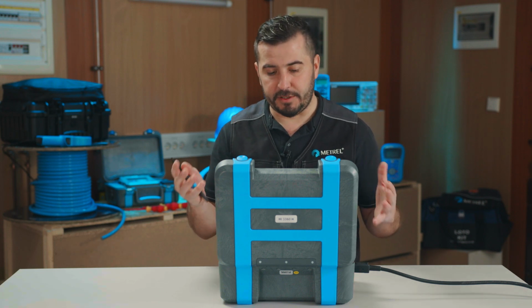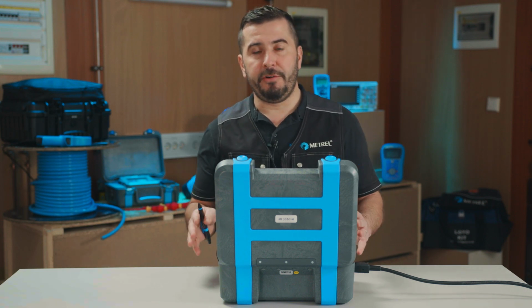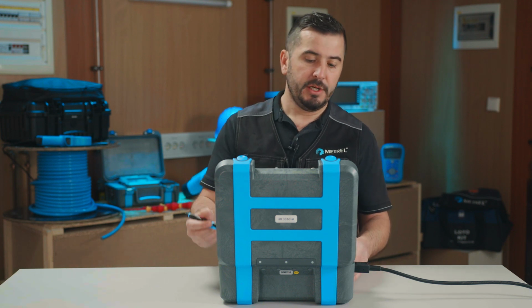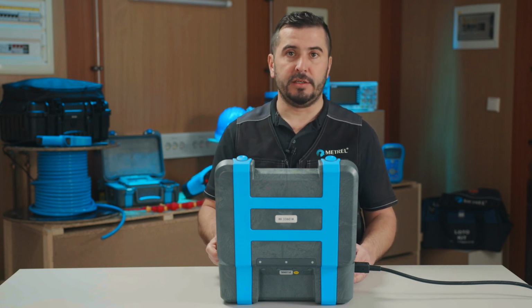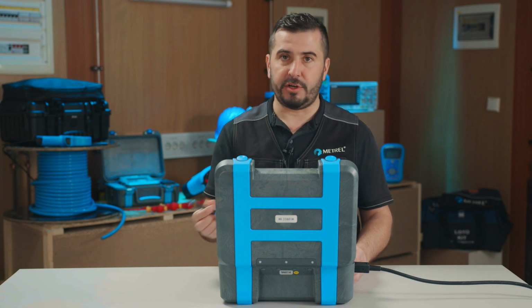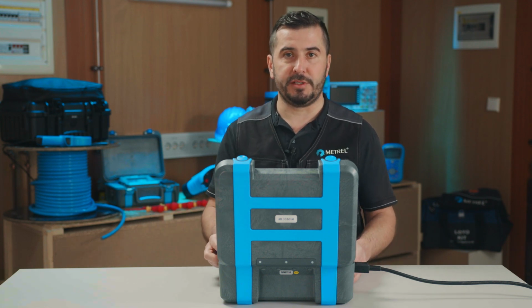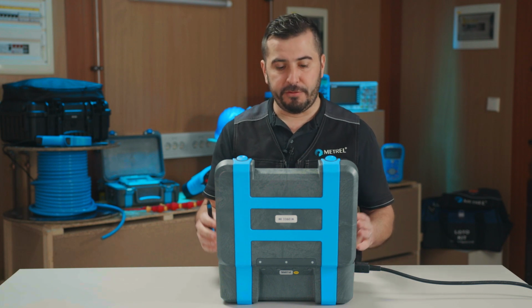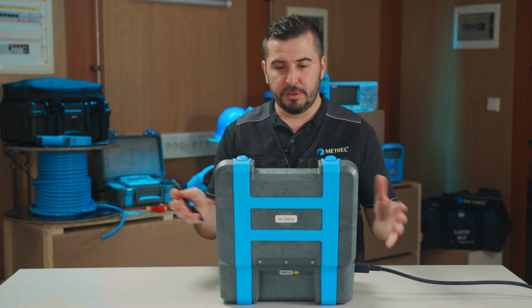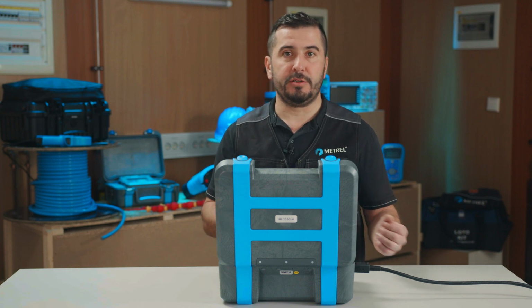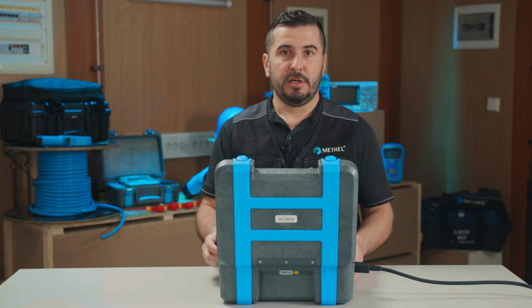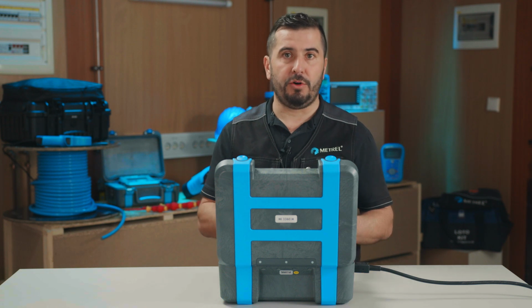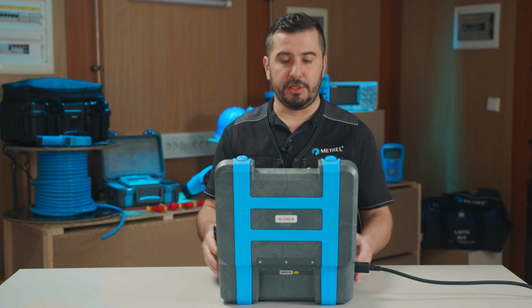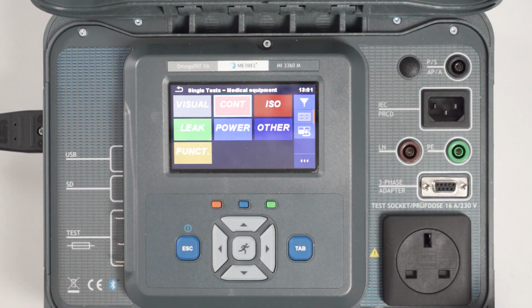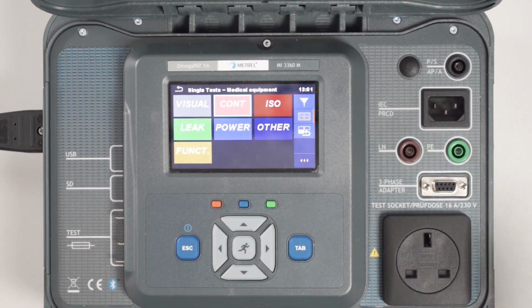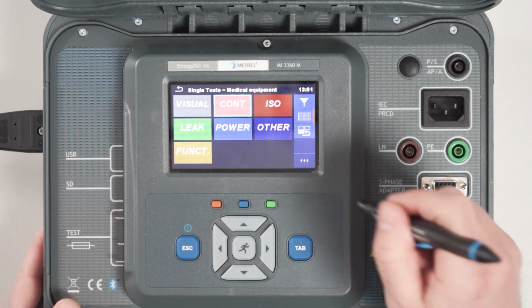So in case that you have an appliance which has somehow failed during the auto sequence procedure, you can simply jump inside the single test menu and try to repeat just a specific measurement to be sure whether it failed due to some inappropriate connection, maybe there was some loss of connection during the test, or the device itself is actually damaged. What kind of measurements are available and which options are available inside this single test menu?